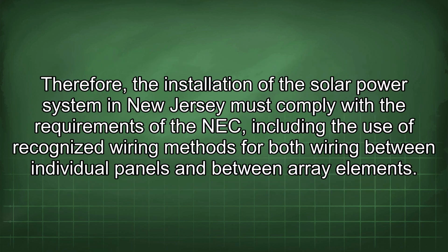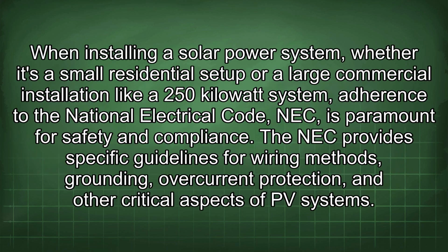Therefore, the installation of the solar power system in New Jersey must comply with the requirements of the NEC, including the use of recognized wiring methods for both wiring between individual panels and between array elements. When installing a solar power system, whether it's a small residential setup or a large commercial installation like a 250 kilowatt system, adherence to the National Electrical Code (NEC) is paramount for safety and compliance. The NEC provides specific guidelines for wiring methods, grounding, overcurrent protection, and other critical aspects of PV systems.